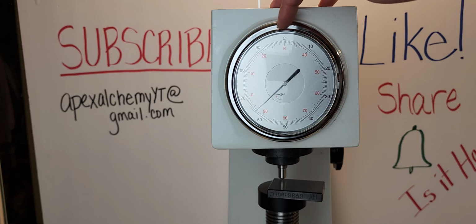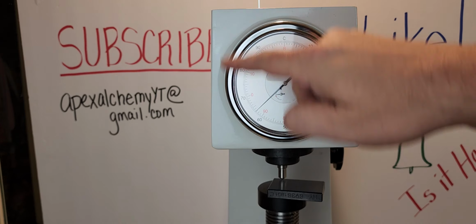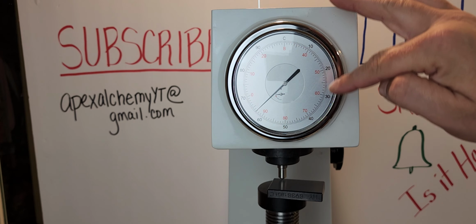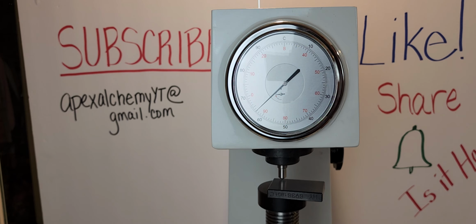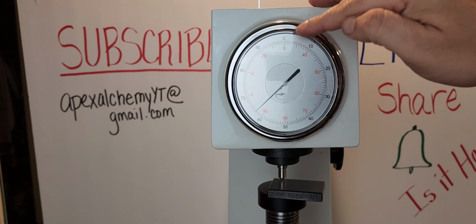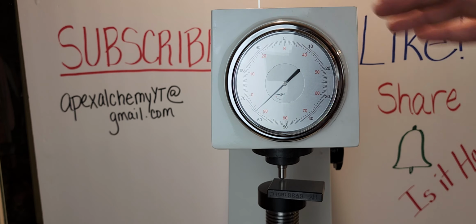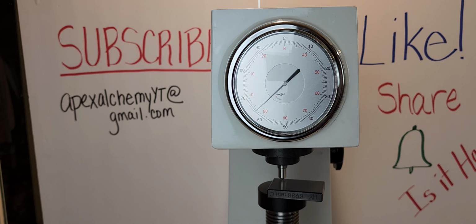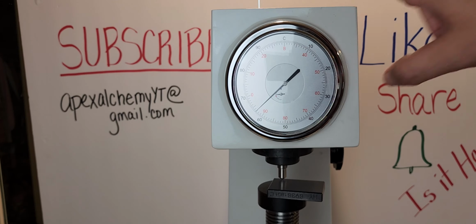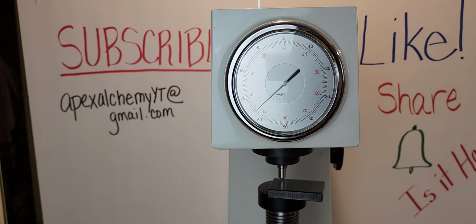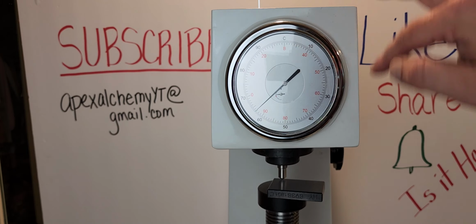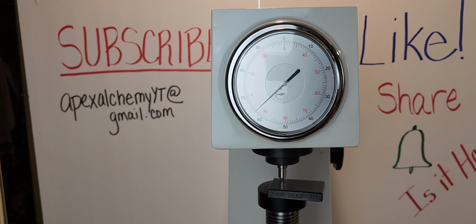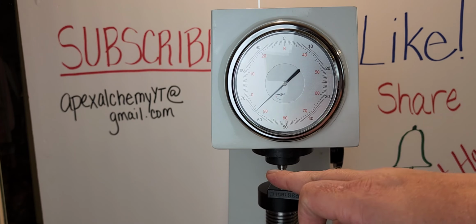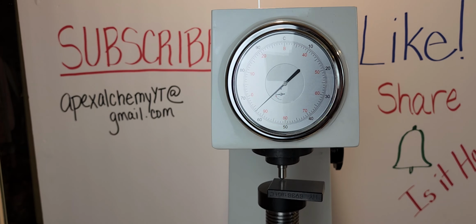And what that means is HRC scale is for hard steel. HRB scale is for plastics, I think. You can use this for plastics, and you have to have a totally different calibration block for that. Anyway, I guess you want to test the hardness of your G10 or your Micarta or whatever like that. You can use the B scale to do that. But for this, for the HRC, for hardened steel, we use the C scale.